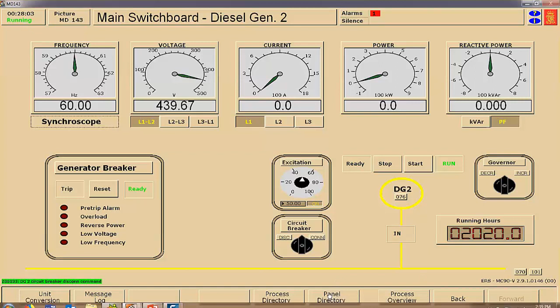Same procedure. And we're going to end up with both diesel generators offline with just the steam turbine and the shaft generator on. Disconnect. So number 2 is off the line. So now I'm going to put the shaft generator on. So we'll go to shaft generator. Same thing as before, synchroscope, shaft generator. Let's increase the speed of it slightly. That looks about right to me.